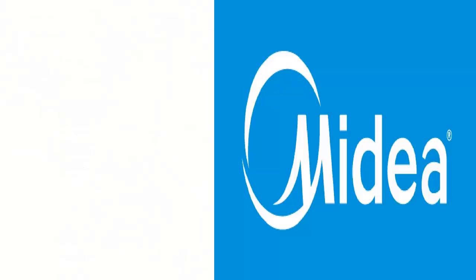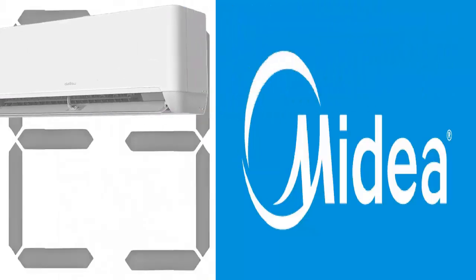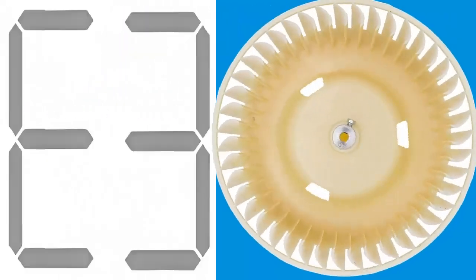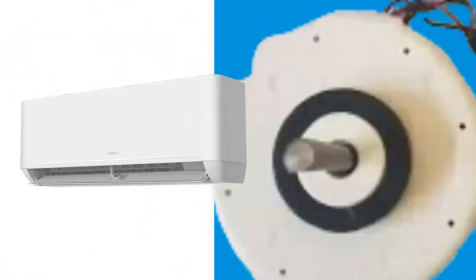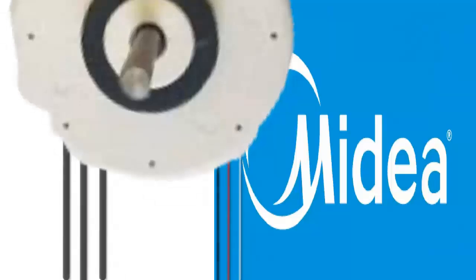In this video, we will address the solution to problems related to the indoor unit fan of MIDEA air conditioners, identified by the error code E3. We will focus on 6-wire fans, composed of 2 sets of connections, 3 thin wires and 3 thick wires. These fans operate with a Hall effect sensor, and do not require a relay.